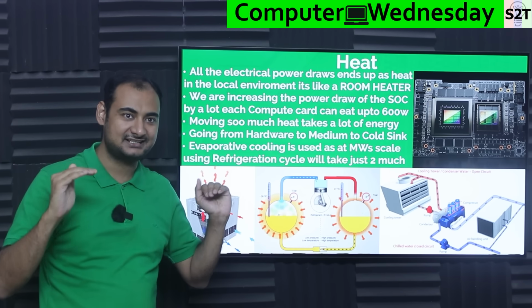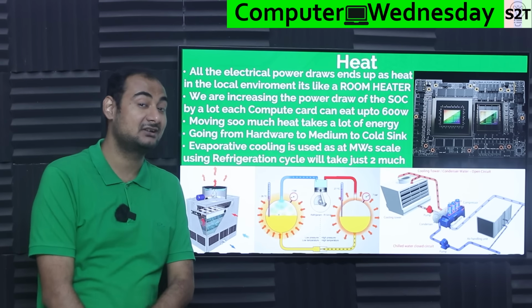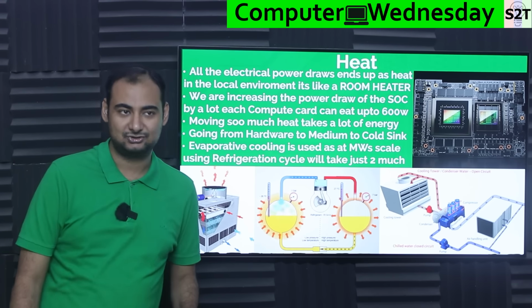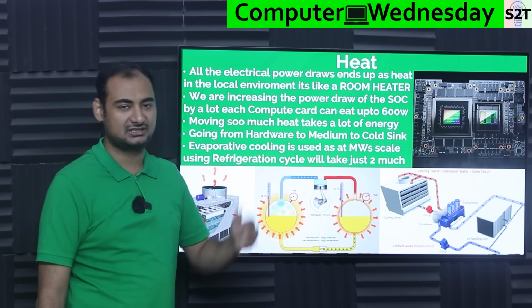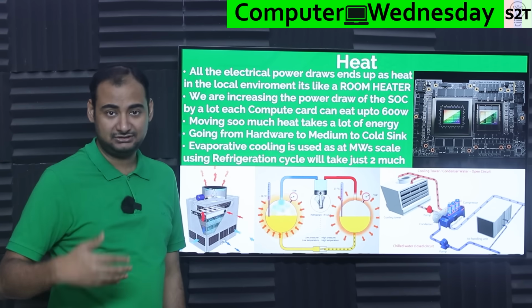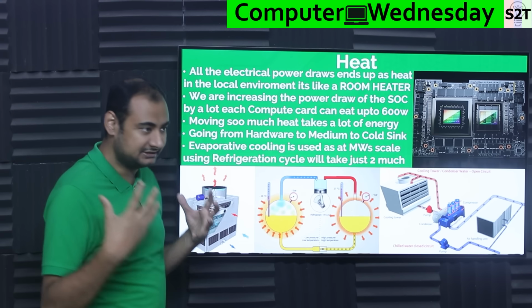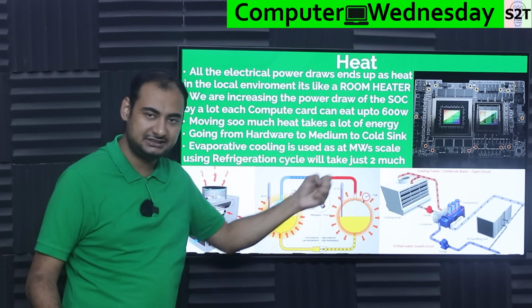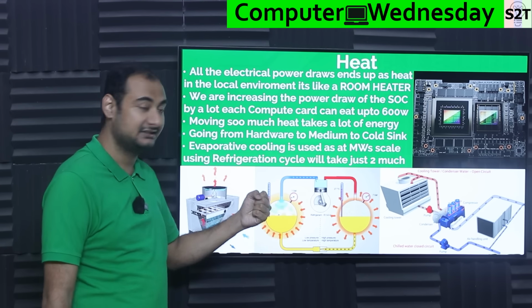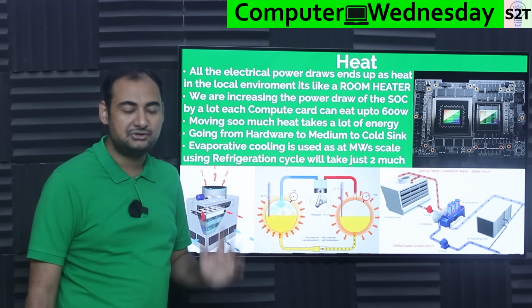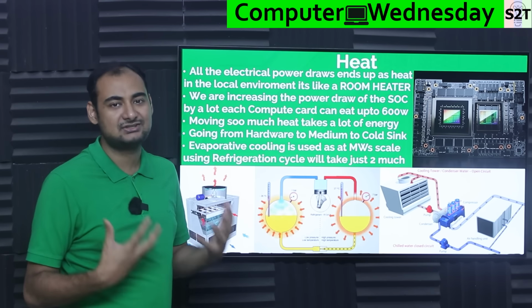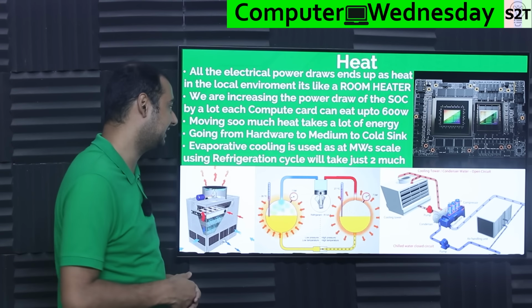You have to design things that can work at 65 degrees. That's why people are looking into CO2 supercritical systems and all that, which could work at that sort of temperature. Right now, if you have a direct coupled system - basically take the heat from one side of the refrigerant and dump it into air - it will just not work. It just does not have enough oomph to do that right now.